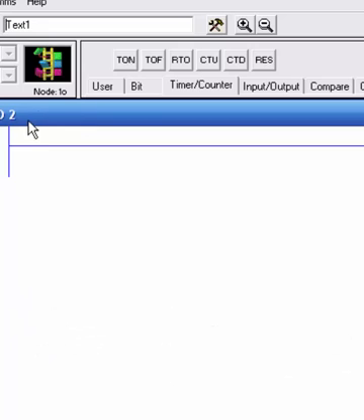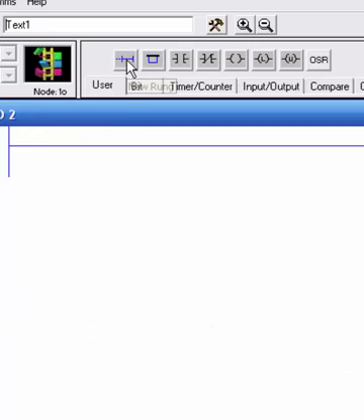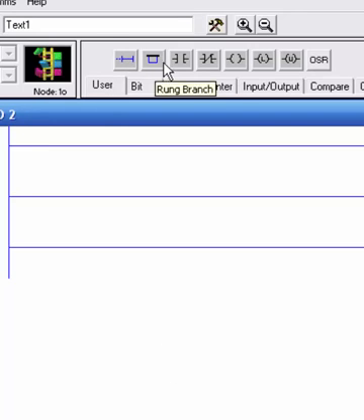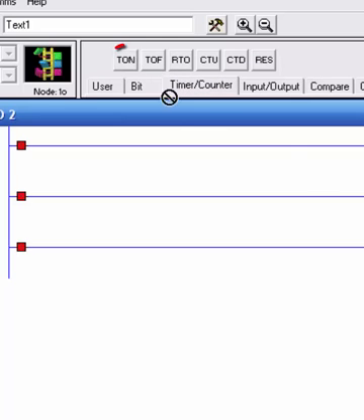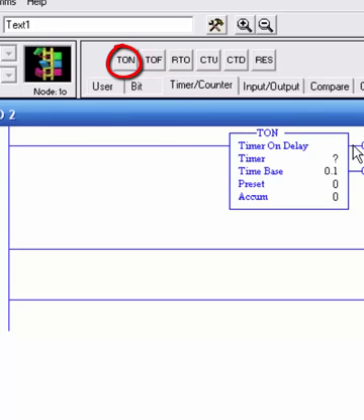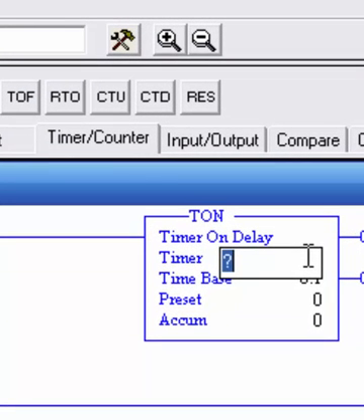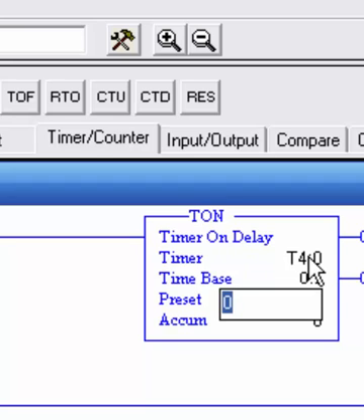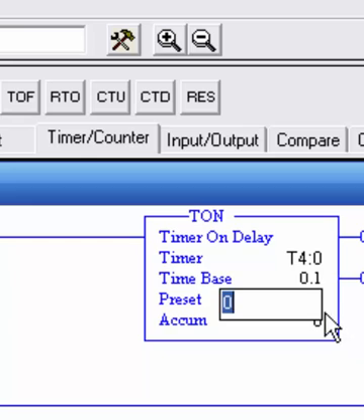The most basic would be the Timer On, so I'll add a few rungs here and grab the TON and drop it here - it always ends up appearing on the right-hand side. Timers always start as T4, so I'll say T4:0, and then we pick a time base. This is going to be tenths of seconds. On RS Logix you have more choices: one second, tenths, hundredths, and thousandths.